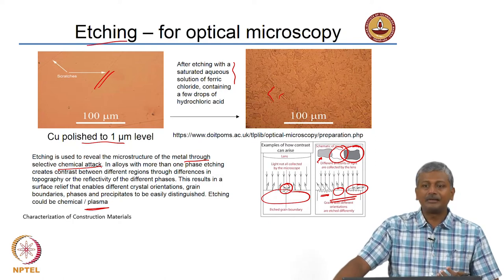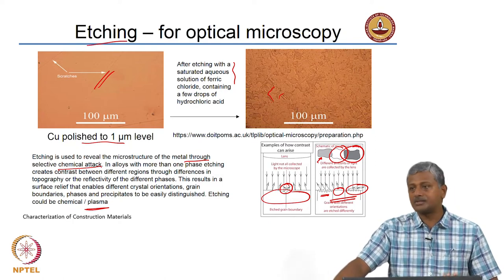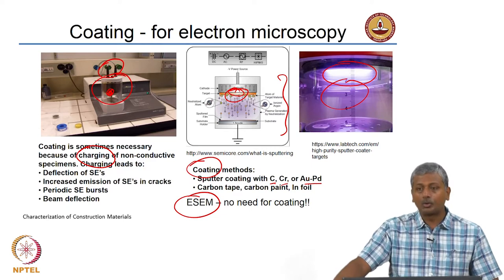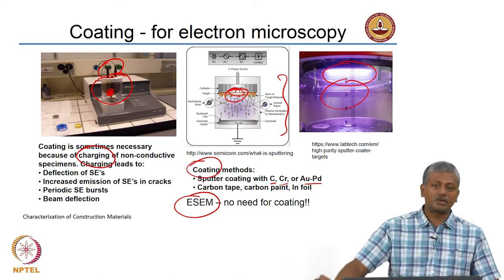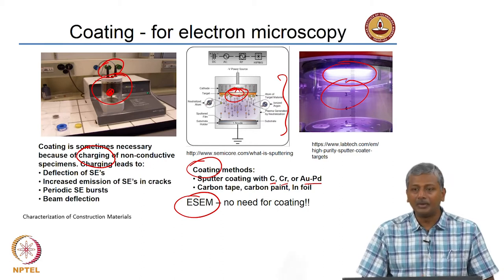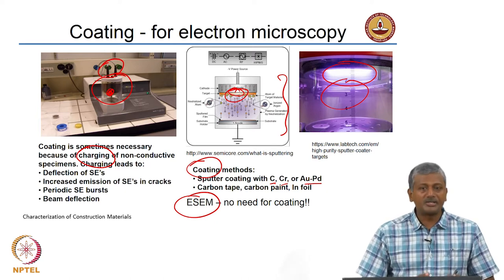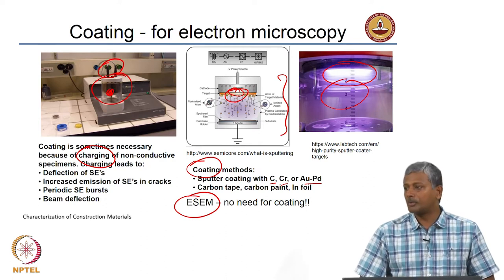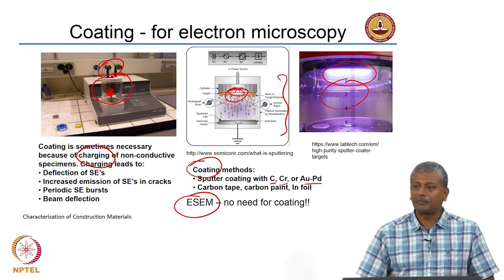We talked about certain additional aspects of specimen preparation. One is etching. Etching is basically selective chemical attack which exposes certain phases and exposes the grain boundaries in a much better fashion than if you just do polishing. Finally, we talked about coating, which is recommended for samples that are non-conductive. In non-conductive samples used in a scanning electron microscope, the electron beam tends to charge up on top of the specimen because there is nothing to conduct the beam down towards the metallic parts of the microscope. So we need a conductive surface, typically obtained by sputter coating with an element like carbon, chromium, or gold-palladium, applied as a layer on top of the specimen.